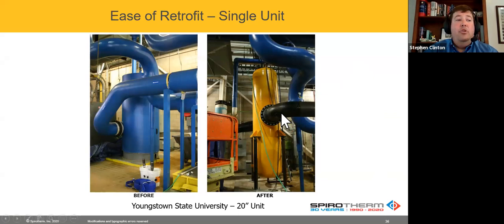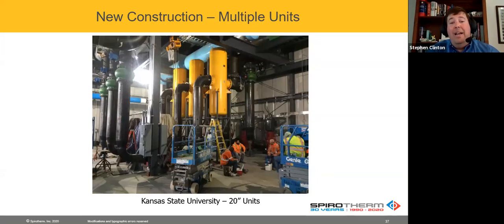So we can retrofit. The nice thing too is short radius elbows are fine. Traditional air separators are supposed to have straight runs of piping. We don't have to have that. The other thing is Kansas State University, these are big guys. Those are 20-inch pipe connections to give you some frame of reference. Nice thing too is there are 2 future units slated. I wanted to show this to you because these short radius elbows are perfectly fine. This is also something the owner and the engineer said: if something gets in, maybe a grocery bag or some debris from construction, it may get caught right here. Well, this is the isolation valve. This is a blind flange. Isolate the unit, swing the flange down, remove anything that's fouled it, and then move along. So new construction, retrofits works very well.